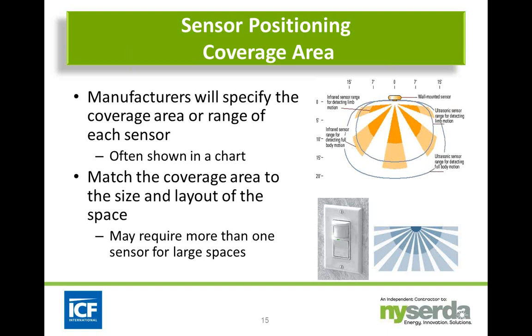You want to make sure you match the coverage area to the size of the space that you're working with. So you may be able to use one wall-mounted sensor if the switch is positioned correctly and it's a smaller classroom. Or you may need a couple of ceiling-mounted sensors to create the right kind of detection space. You may need more than one sensor based on the different size spaces. So you want to take this all into consideration when you're specifying and installing your occupancy sensors.